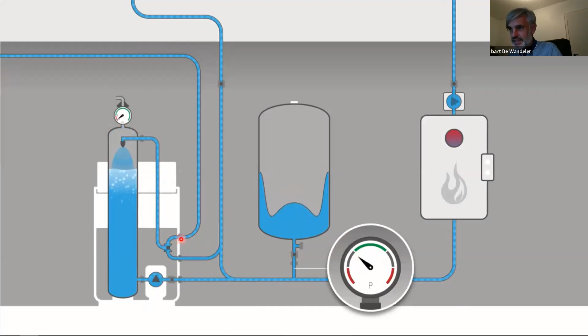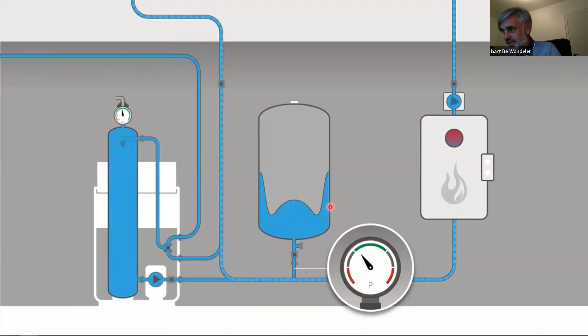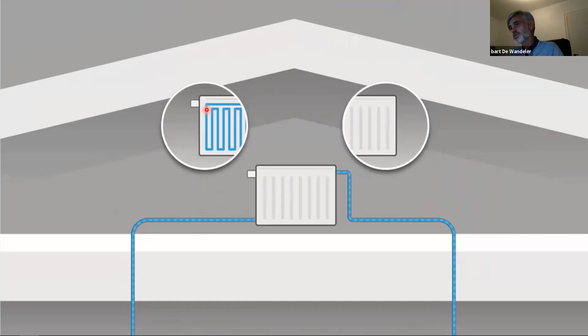We get a signal and bring city water into the cycle. We degas it and put completely degassed city water into your closed system, so we can provide the correct minimum water level for your expansion tank. You can also see that the air in the system is going away and it becomes full of water, which means your system has a perfect heat or cooling transfer across all installed equipment.